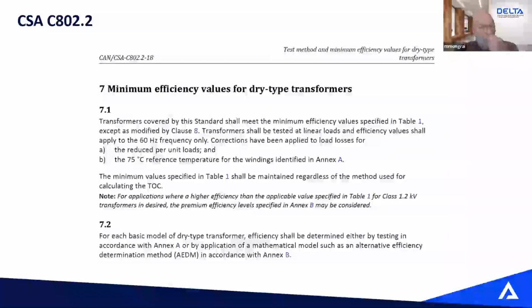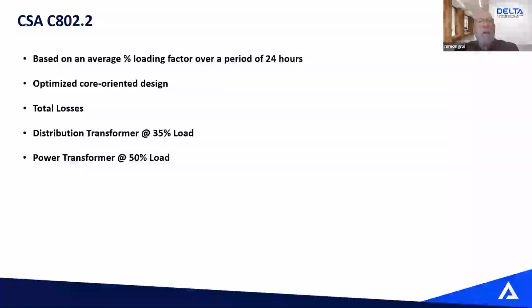Of course, not all transformers need to be compliant with CSA C802.2. There's lots of variation in the offering and what needs to be compliant. So mainly, I would say the reason for CSA C802.2 is to base your efficiency on a loading over a day. It's based on the core losses, so the no load losses of a transformer. It's also based on your total loss, and the most important thing about that standard is the efficiency that we need to be compliant with. For low voltage transformers, we need to meet that at 35% load, and for power transformers, we need to meet that at 50% load. So it's quite low in regards to loading.